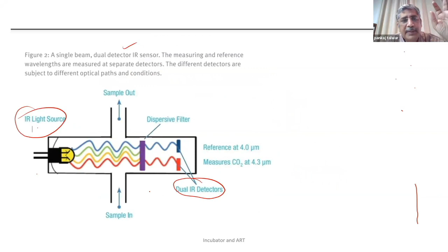Then there's IR detection here and IR processing here. There are interference filters and there's a bulb placed here. The bulb will give you 4.3 micrometer light, so it is an IR light source. It's a dual detection IR sensor. They put dual IR detectors here for a better outcome. The light is burning here. Nowadays we have better sensors. As you see here, we have a mirror surface from which the light is thrown, and the gas is checked here and we get the change. Basically it works at 4.3 micrometer light.